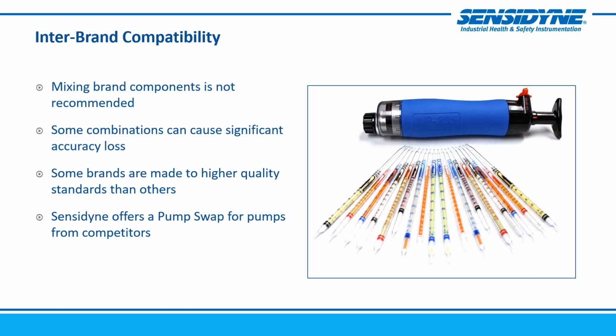Some brands are made to higher quality standards than others. Note that even if it did fit tightly, because that brand might not hold the same quality standard, it could significantly impact the reading. For this reason, Sensidyne offers a pump swap program, which I'll talk about momentarily, and which allows you to consolidate if you need to. If you have a different company's pump but want to use our tubes, and you buy, I think, a set of 12 boxes of tubes because you have a lot of sampling to do, we can offer a pump as part of our pump swap program.